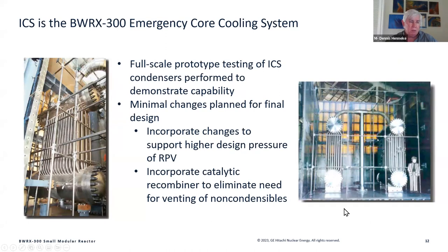And here's just the actual isolation condenser we tested for ESBWR. So we have gone through prototype testing of these. There is some additional testing because we have added to the design, which was not on the ESBWR, catalytic recombiners. We're going to bottle up the primary, and we're going to have any sort of radiolytic creation of non-condensable gases, hydrogen and oxygen, in the isolation condensers. And so we're adding those in, and we're going to have to do some testing, but that is part of the design.